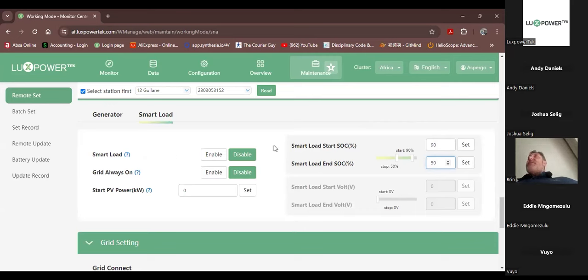And AC coupling means that if you have an existing Sunny Boy or a grid-tied inverter, in other words, an inverter that just harvests solar and supports or supplements the loads, you can now connect it to an SNA, which then turns your Sunny Boy into an inverter that can now store power in batteries, all right? So we will also use the smart load port for that.